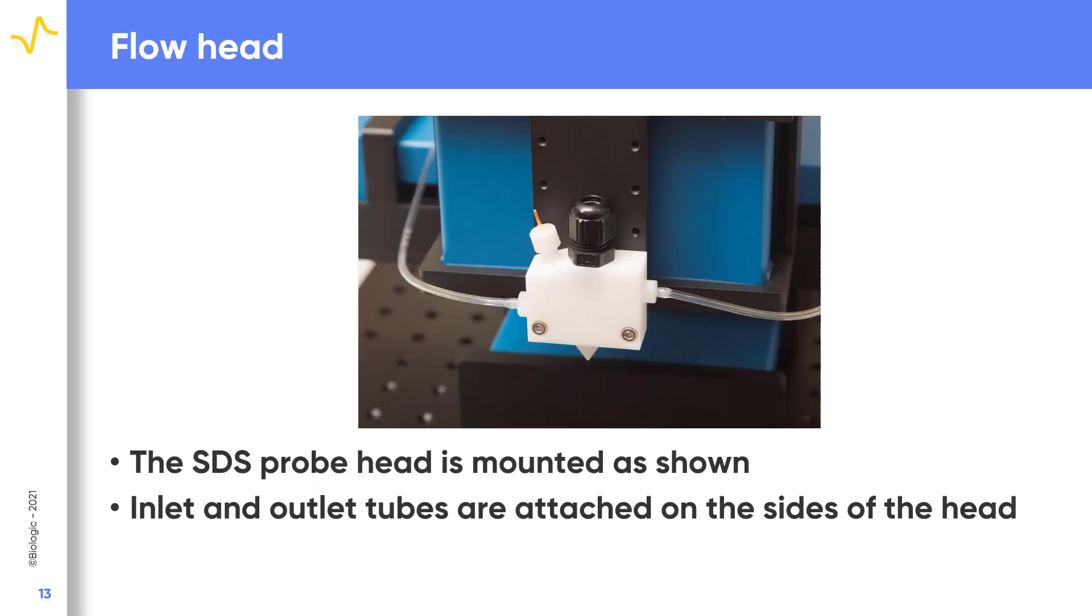As a key component to the SDC experiment, let's take another look at the SDC heads. The flow head supplied with the M470 is shown mounted on the scan head. In this image, we see the inlet and outlet tubes mounted on the head, and the counter electrode is also shown.